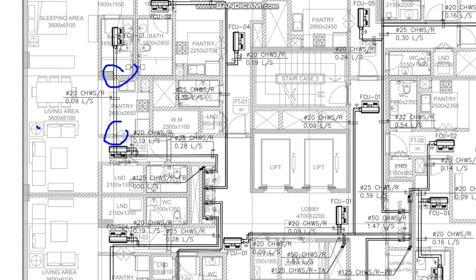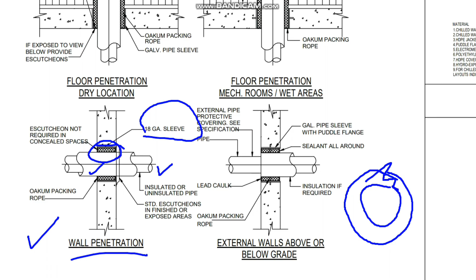When it comes to the mechanical or HVAC engineer and civil engineer, we have to consider one important point. For example, this is the pipeline, and this is the insulation with cladding. We have to provide the GI sleeve over that, and there should be a minimum 25mm clearance on all sides - for example 25mm here and 25mm here.